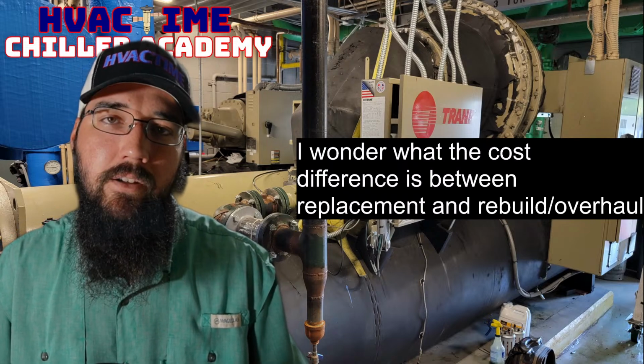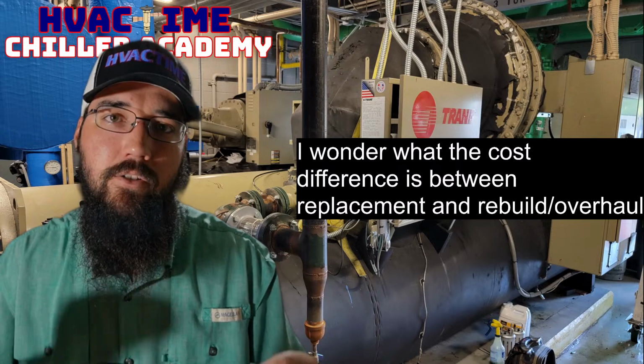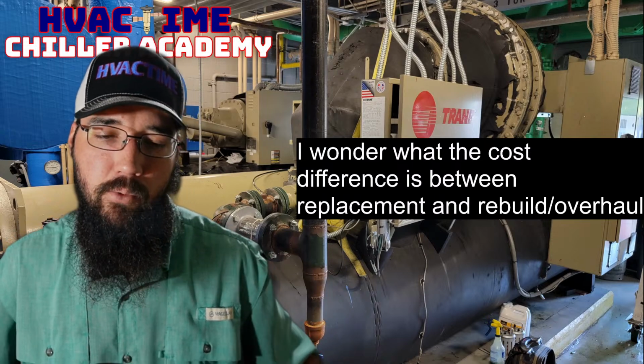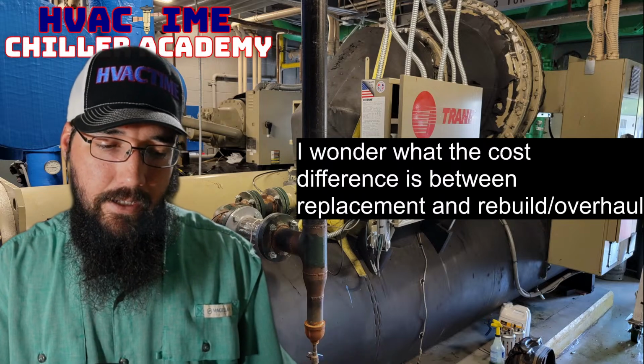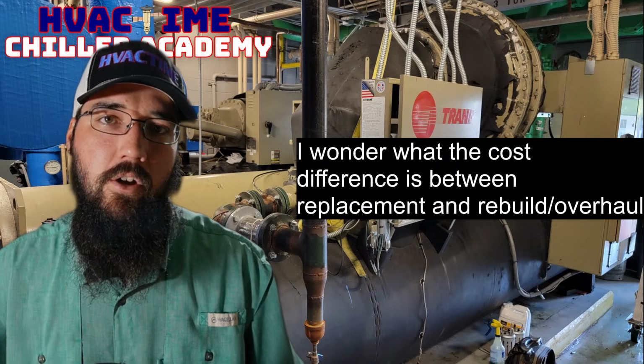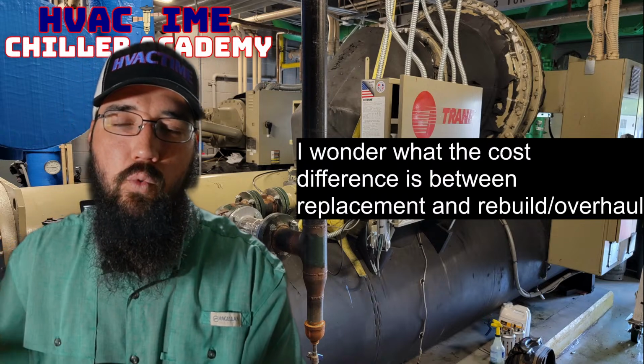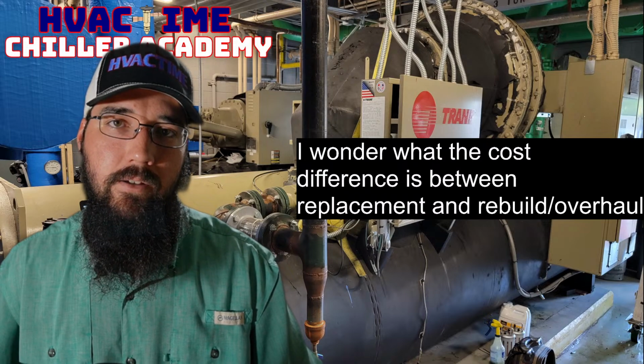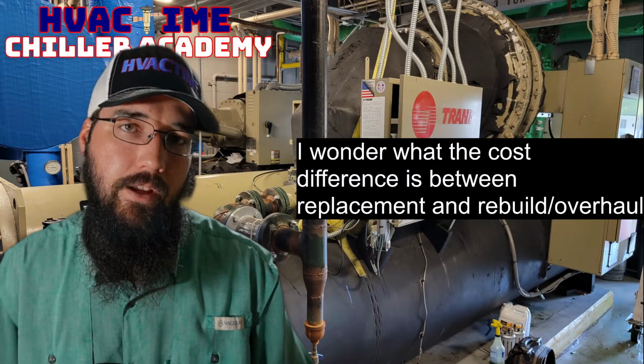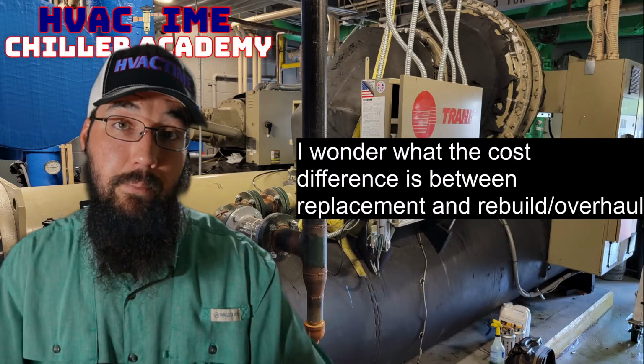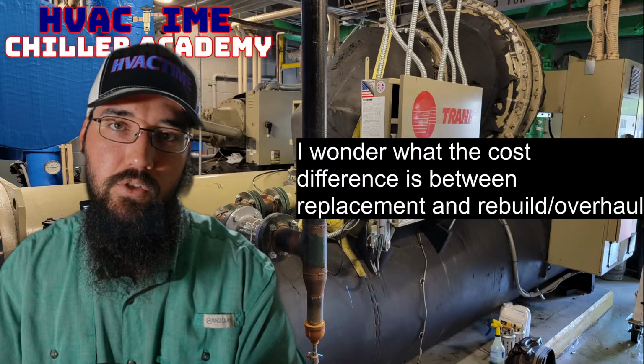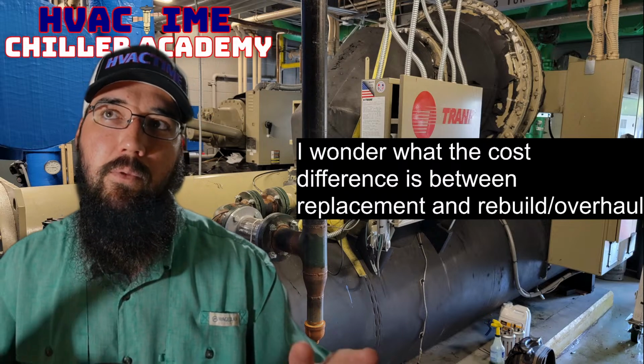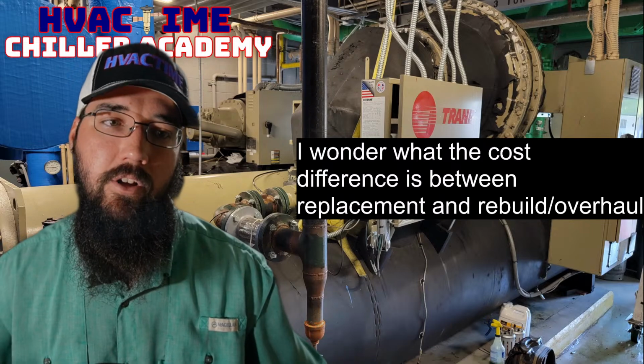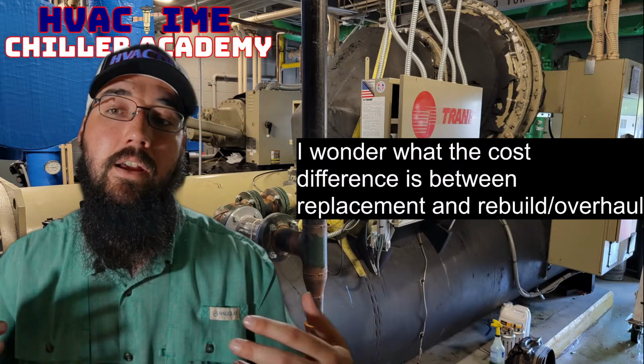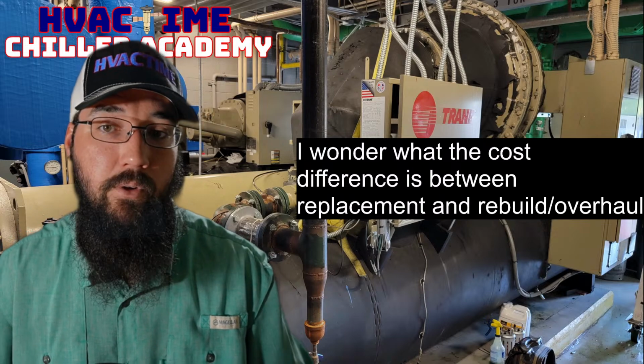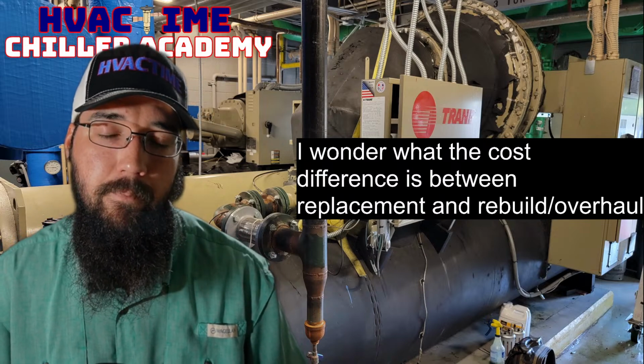These machines, when used and repaired correctly, I think is the major point here, can be a career-long machine in ways you wouldn't expect from the others. Your condenser coils are going to be the main issue on air-cooled systems, whether air-cooled chillers, RTUs, or splits. The cost to fix those is so astronomical that it removes a lot of the cost benefit to fixing something like that, where you don't have that issue with water-cooled centrifugals.